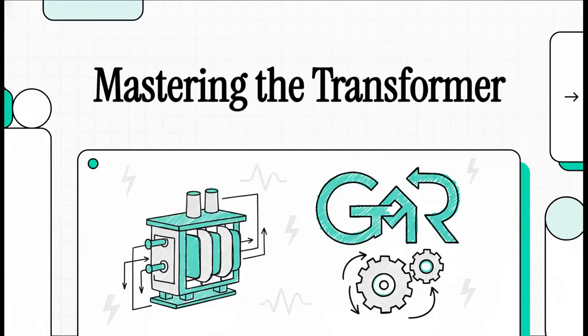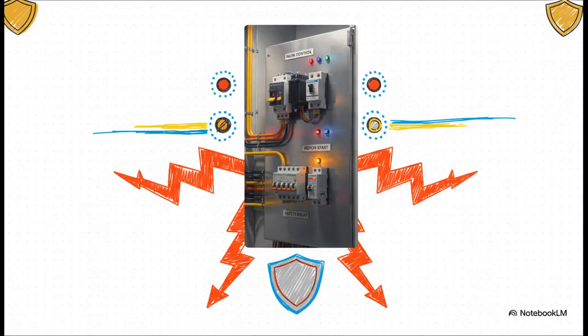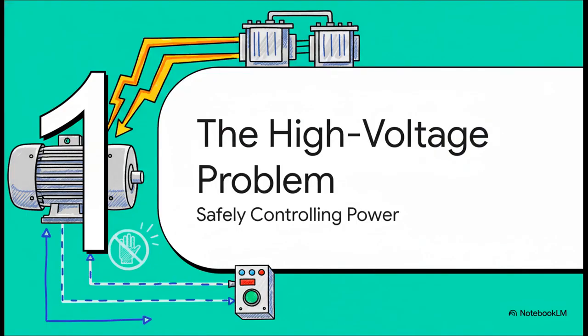Let's jump in. Okay, so you pop open an industrial control panel just like this one. Tucked away inside, there's a hidden guardian. Its whole job is to take that high, dangerous voltage and knock it down to a safe level for all the operator controls. The push buttons, the switches, the pilot lights. That little guardian is the control transformer, and its #1 job is keeping people safe.